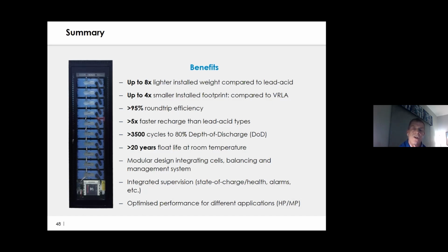They charge, the lithium ion batteries charge much faster, 5 times faster than the lead acid batteries. Again, they can do 3,500 cycles of deep discharge recharging. So you can discharge them to 80% level, so 20% capacity. You can do that 3,500 times, then recharge them back up again to full capacity, and they'll work without a hitch. You can't do that with the VRLA batteries. It's about 1/10 of that. 20-year life at room temperature. That for all batteries, that's rather important to keep them at room temperature or keep them in a controlled environment.